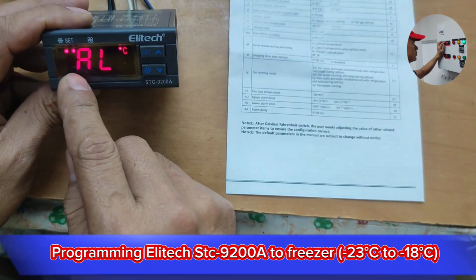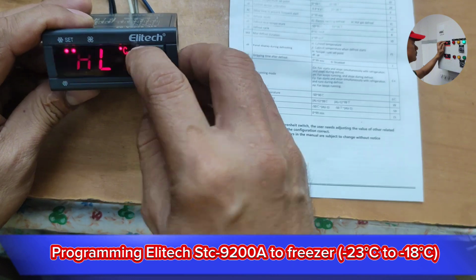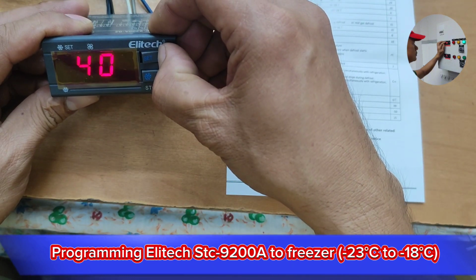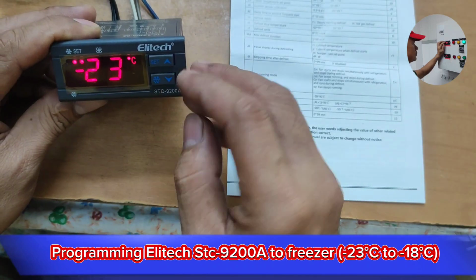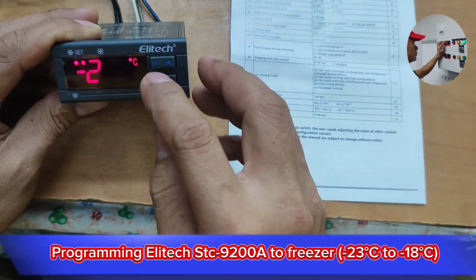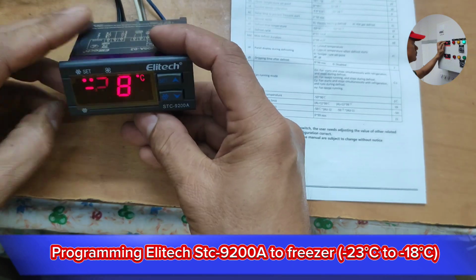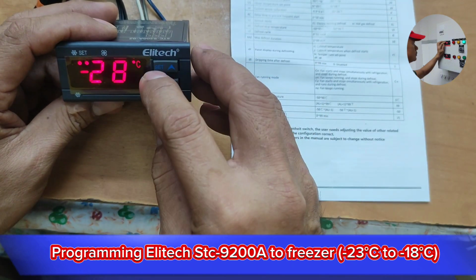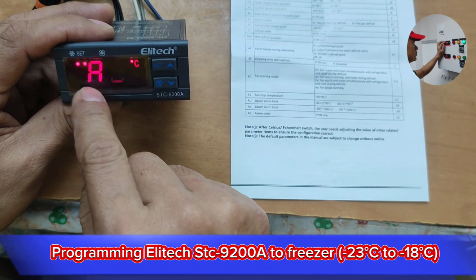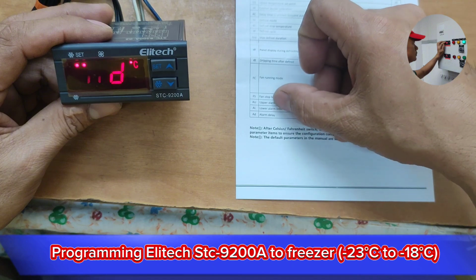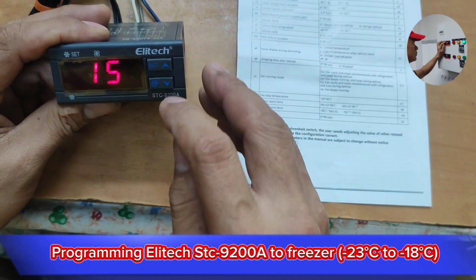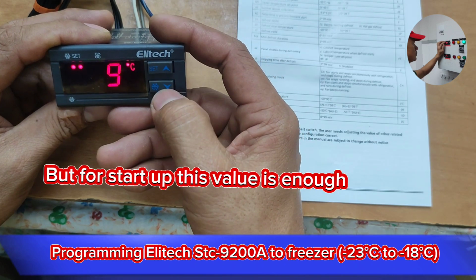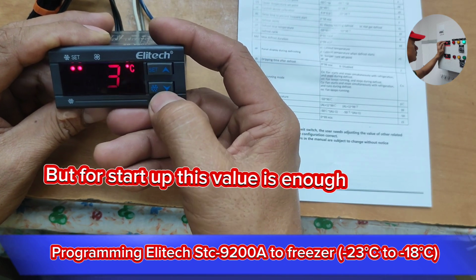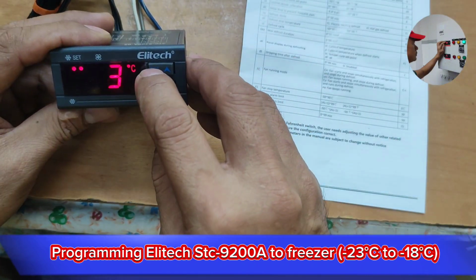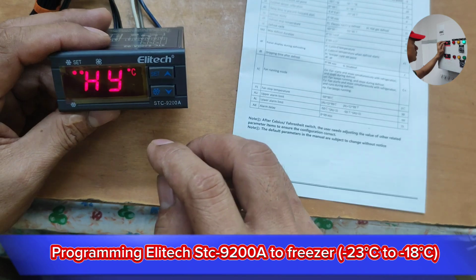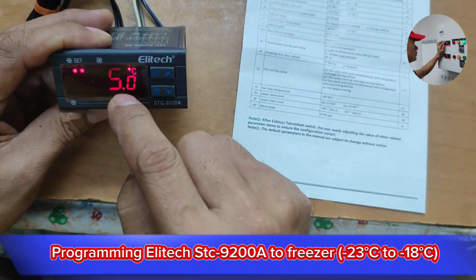Then preset. And the lowest temperature, lower alarm limit, reset. I'm going to set that to negative 28 or 30, because this is my set point, I'm just adding a little bit. Then proceed. So this will be my lowest temperature. Once the sensor reads this value, it will trigger an alarm. Then proceed, and I'm going to delay the two parameters here, the upper and lower alarm limit. Reset, 15 minutes is overkill. We're going to set that to 3 minutes delay prior to the activation of this alarm. Reset, and we're all done with the programming. Reset again. Five, I'm going to explain that briefly.